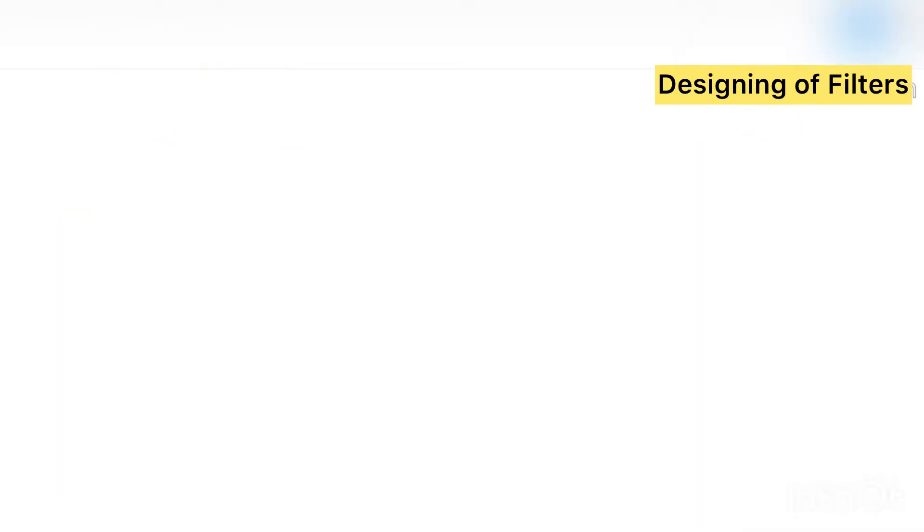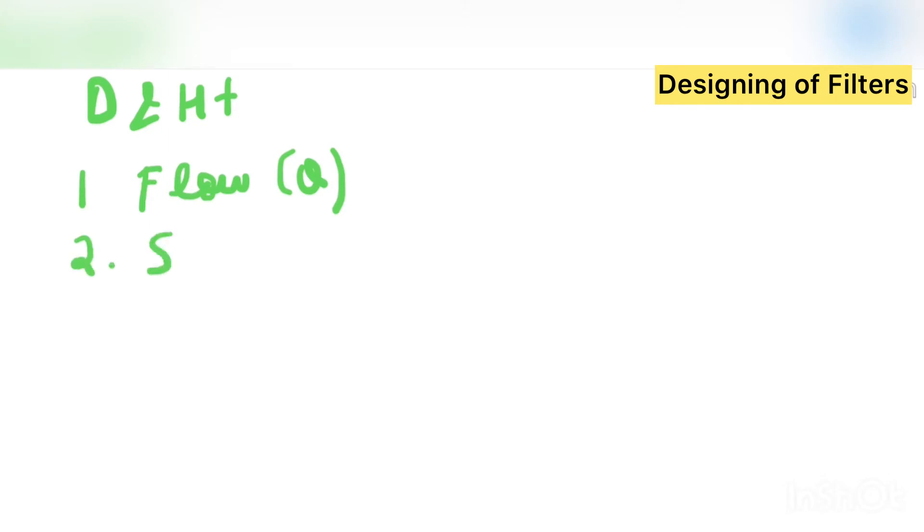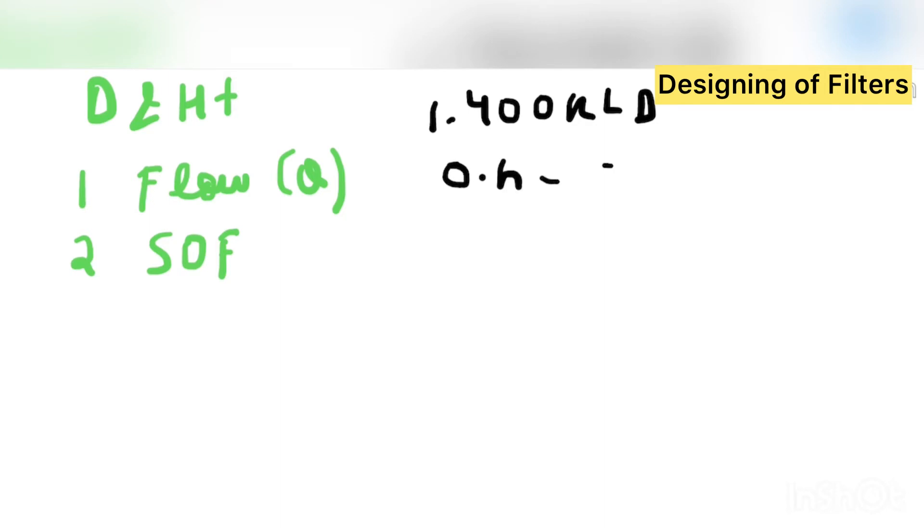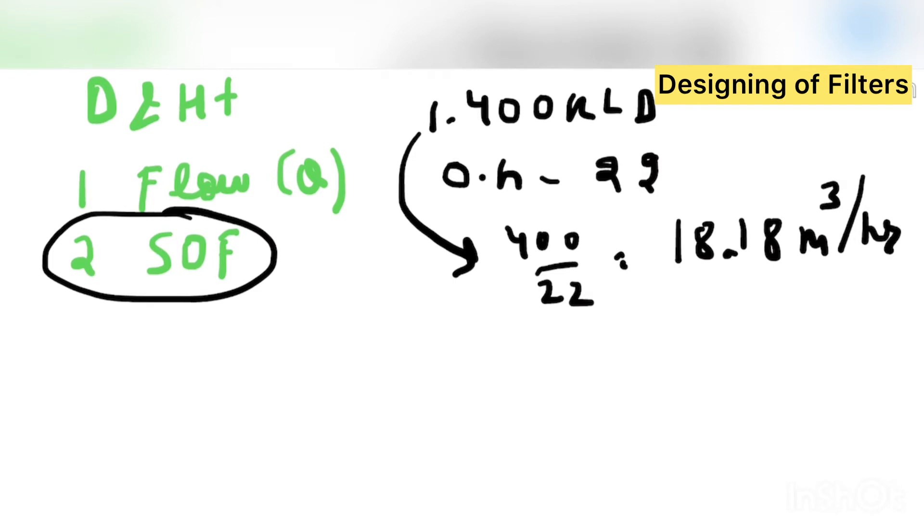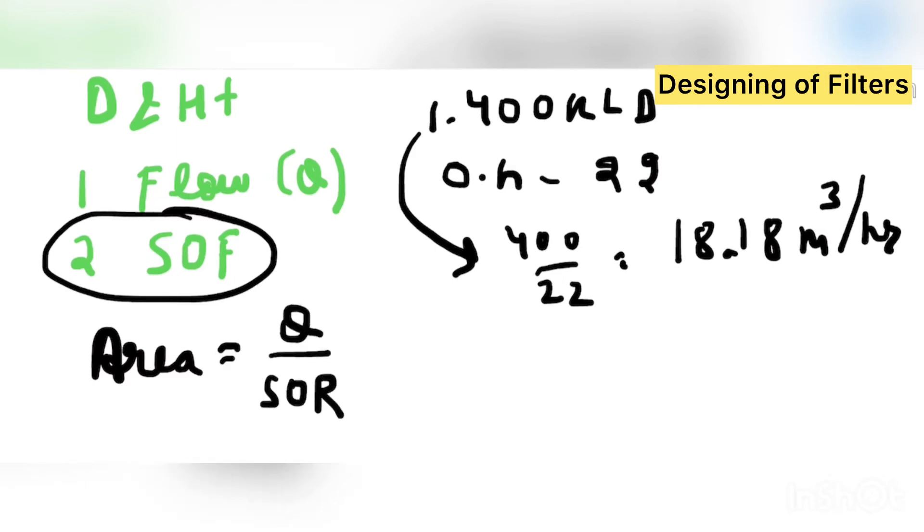First of all we know that for designing the diameter and height, we should know what is the flow. Flow is Q. And second is the surface overflow rate. So flow, suppose I will take one example. The example is of 400 KLD plant. So 400 KLD plant, I am saying that operating hours are 22. So this can be, if I compare it to the meter cube per hour, so 400 divided by 22, that will give me 18.18 meter cube per hour. Now surface overflow rate is very important.